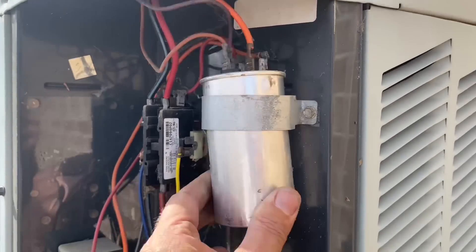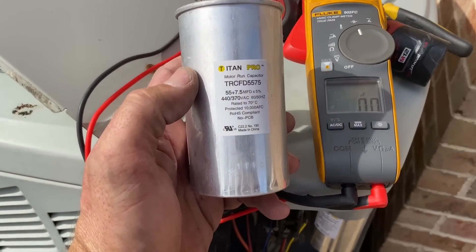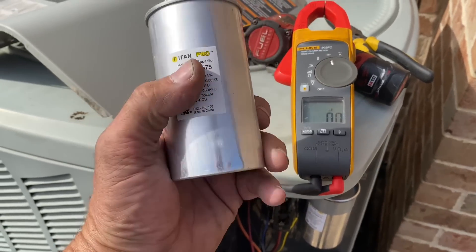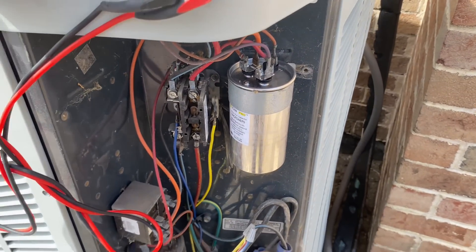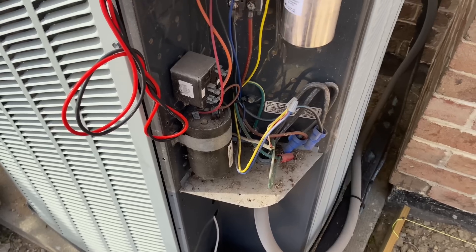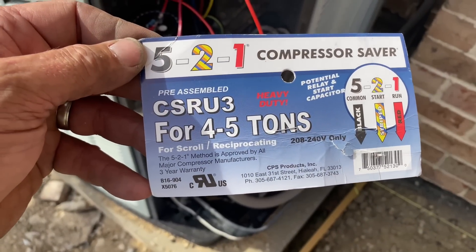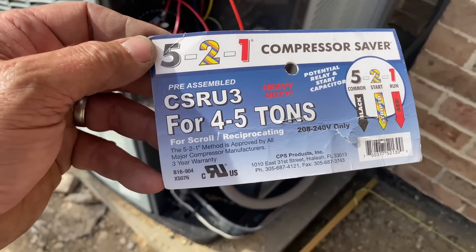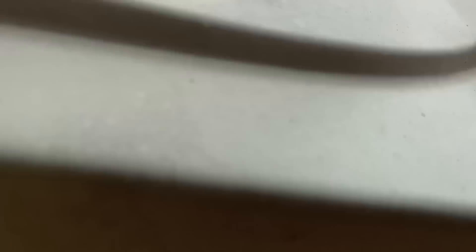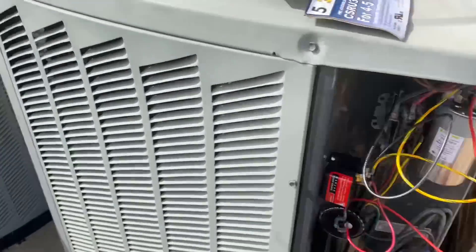The capacitor doesn't look bloated. Titan Pro — pulled the dual capacitor, 55 over 7.5, and it's reading 53 over 7.5. But I wasn't testing, I guess. I put a new capacitor in and the same exact thing happened again. So we're going to pull out the hard start, replace that, and she should be good to go. Using the 5-2-1 Compressor Saver — the CSRU3, for 4 to 5 tons. I think we're good. Let's turn this on and see what happens.